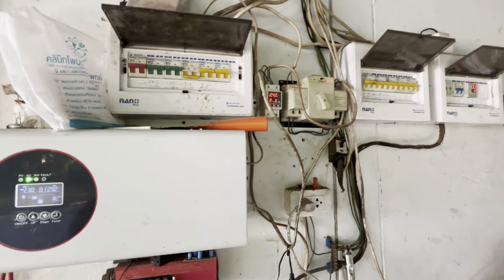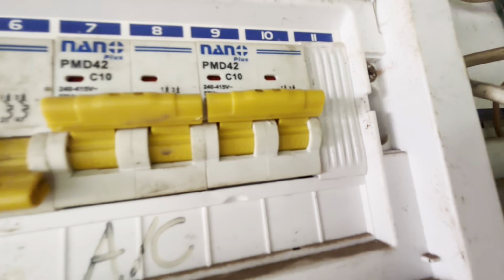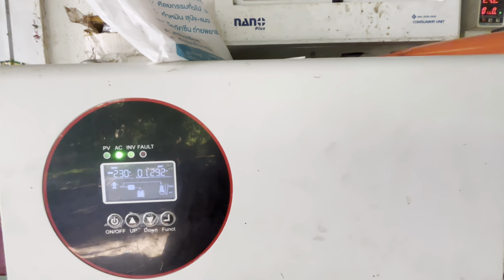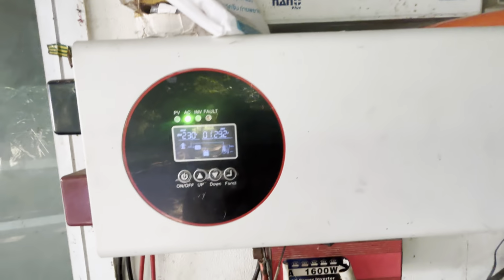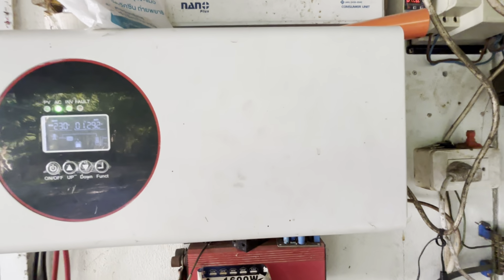That breaker there is the feed going into here, which you'd think is for the battery charger. I've always seen it as the feed for the battery charger that charges these batteries. But it should actually be rated to take 3 kilowatts, which is 12 amps.